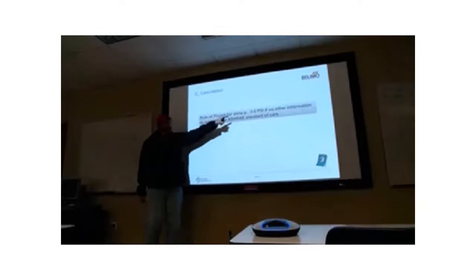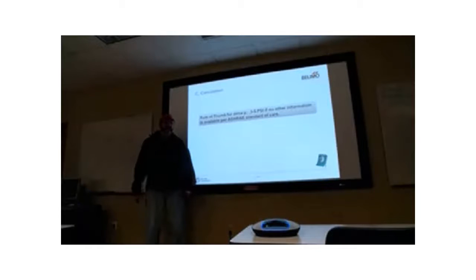Now, these other two things, delta P and Cv. Well, here's the rule of thumb. If somebody put a gun to your head and said you need to size that valve, and you picked a value between 3 and 5 psi to size the valve, you would be on solid ground. That is to say, most people would not disagree with that. In engineering, we call it standard of care. A lot of engineers put this right in their specifications. They say, look, we want you to size these valves between 3 and 5 psi. It's a little bit of an out-of-the-rear-end type of situation, but it comes from years and years of people saying this should be the way it is. I can give you a little bit of insight. It ain't necessarily so, but this is where we start. Okay.